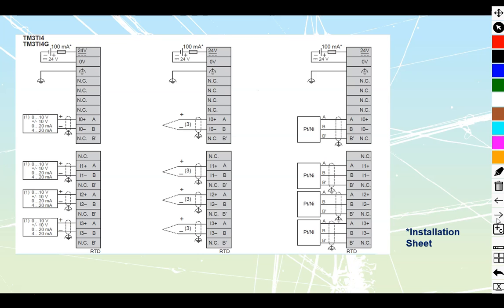Okay, looking at our data sheet over here, we see that the TI4, which is what we're looking at, is broken down across three separate things that we are going to be able to deal with. I can either bring in 0 to 10 volts inside of here, or I can take in my temperature. Again, this is like three-wire RTDs. These are going to be my two-wire thermocouples that I'm going to have.